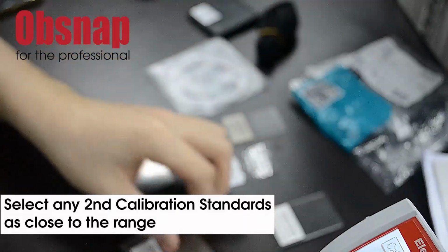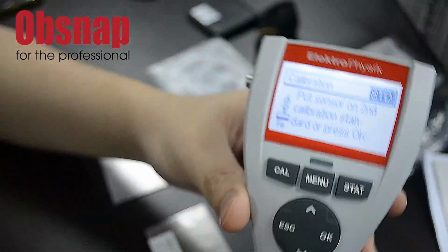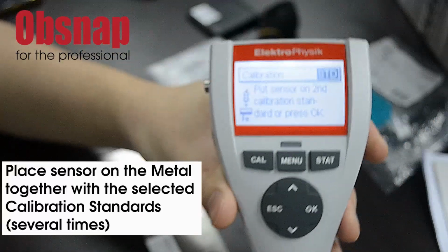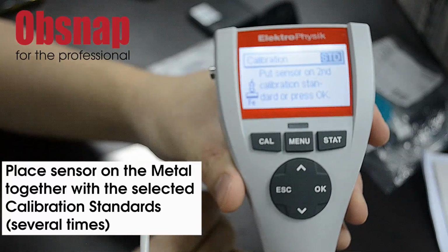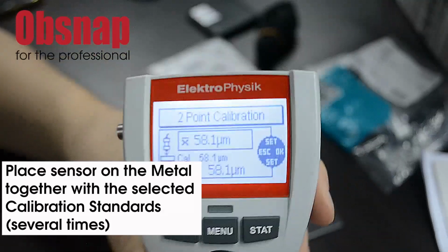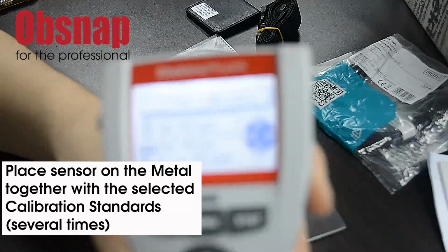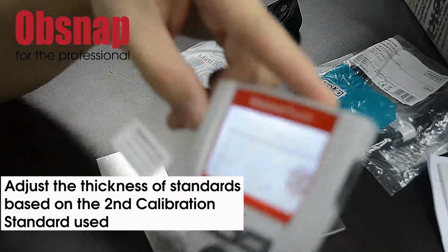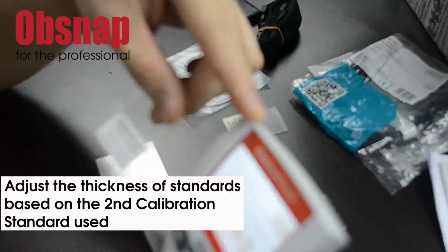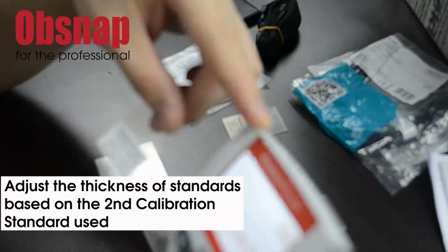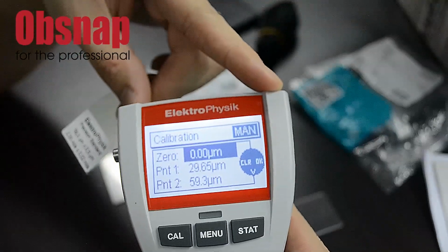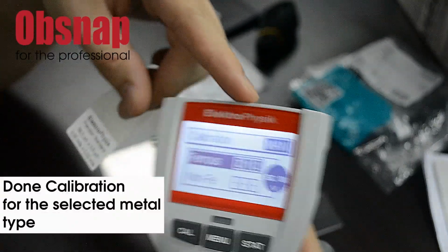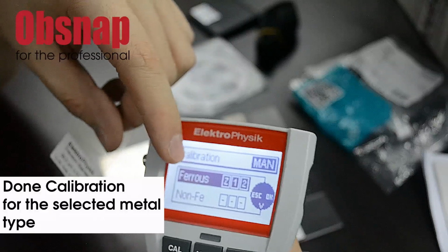Then next we choose another calibration standard and same, place on the metal and place the probe on top of it and you get the reading. Same, you have to adjust it to match the precision standard. So I will adjust it to 29.3. OK. So it shows the calibrations here and you press OK. So here we have done the calibration for the ferrous.